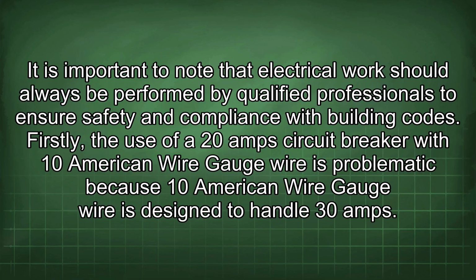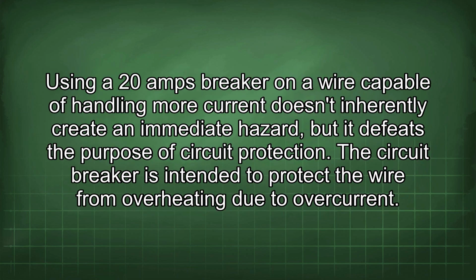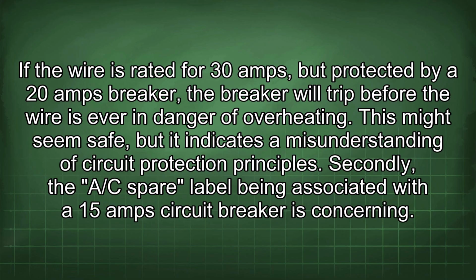Firstly, the use of a 20 amp circuit breaker with 10 American wire gauge wire is problematic because 10 American wire gauge wire is designed to handle 30 amps. Using a 20 amp breaker on a wire capable of handling more current doesn't inherently create an immediate hazard, but it defeats the purpose of circuit protection. The circuit breaker is intended to protect the wire from overheating due to overcurrent. If the wire is rated for 30 amps but protected by a 20 amp breaker, the breaker will trip before the wire is ever in danger of overheating. This might seem safe, but it indicates a misunderstanding of circuit protection principles.